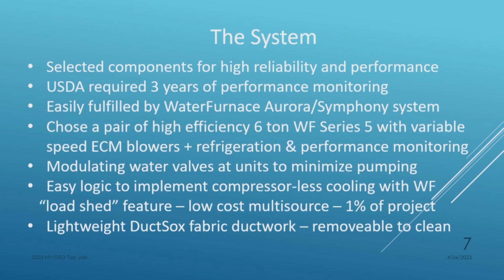So we selected everything for high reliability and performance. I didn't want this thing to not do its job and kill flowers. One of the requirements for the USDA grant was that you had to monitor this thing for 3 years, periodically sending reports showing how much energy you saved and how much you generated out of the ground. This was easily fulfilled by the WaterFurnace Aurora Symphony system, so it was kind of a no-brainer. So we wound up choosing a pair of high-efficiency 6-ton Series 5. Didn't need variable speed on that. If we're going to get Aurora Symphony, we might as well have the full boatload of monitoring and remote control, both on the tech side and on the homeowner side, or the business owner side. So we went for the refrigeration performance monitoring.